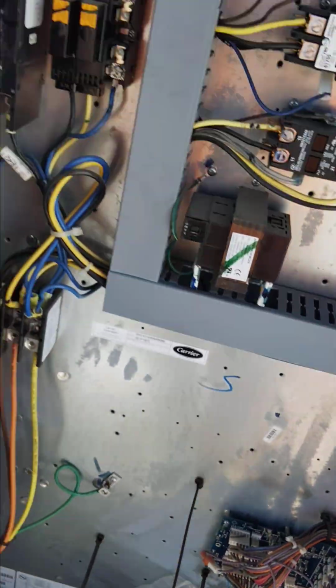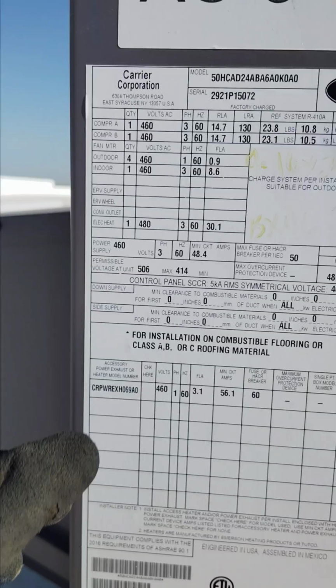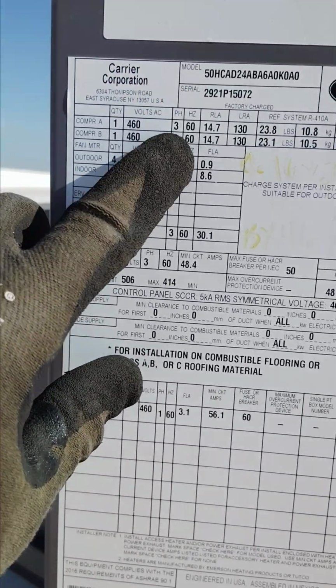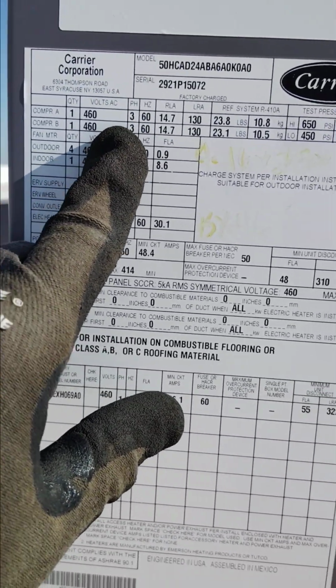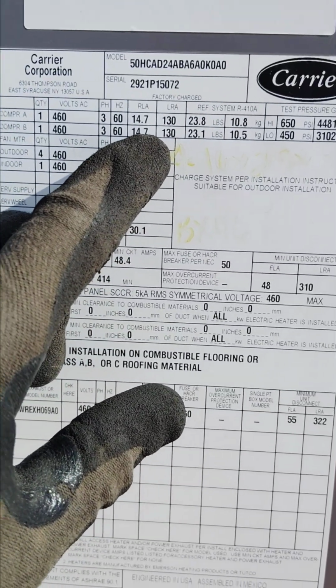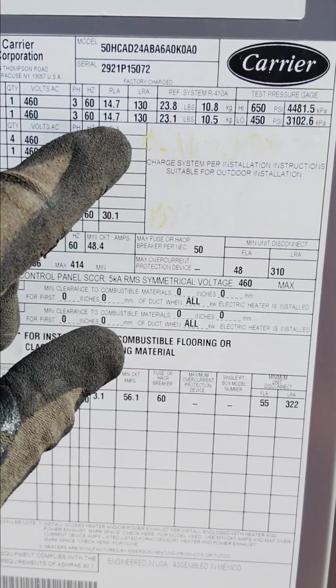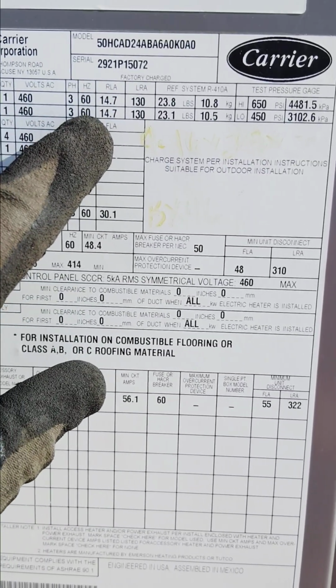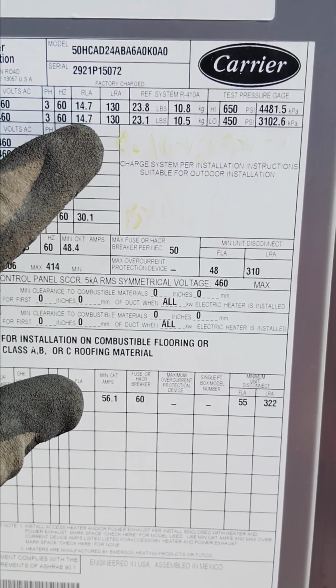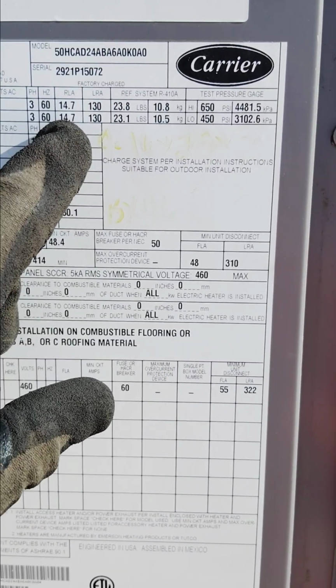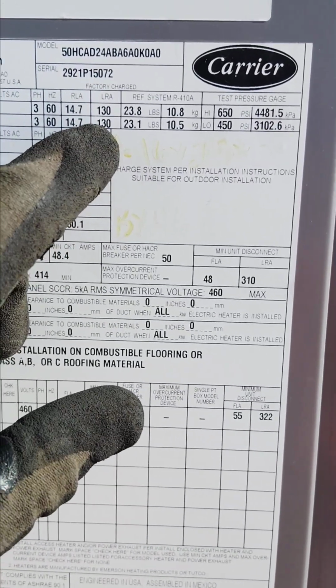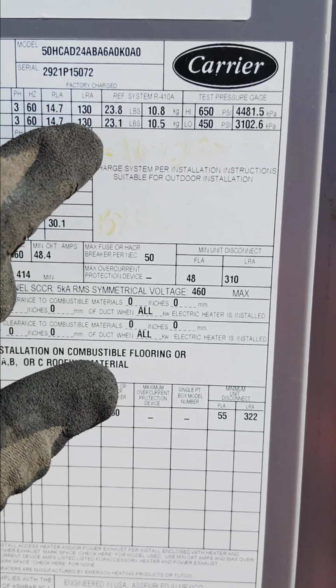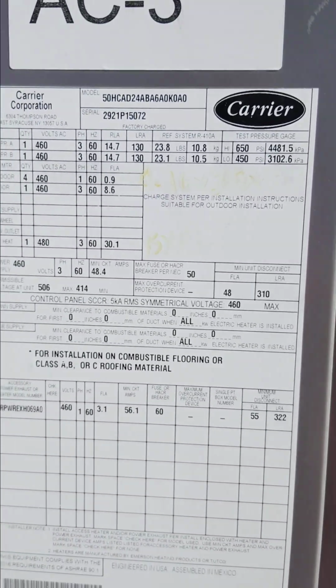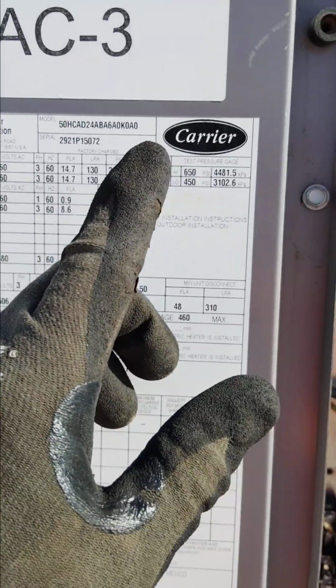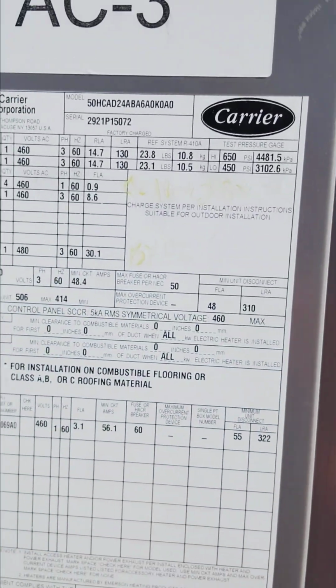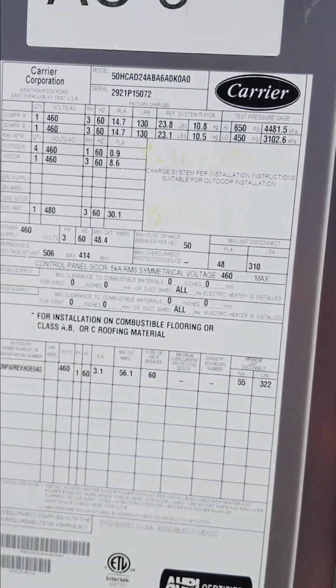As you can see here on the nameplate, these compressors are 3-phase, and it shows the running load amps and the locked rotor amps. So it's supposed to be operating within 14.7. That's for the running load, but normally it's gonna be below that. Once that compressor is locked up or something and it's pulling locked rotor, it's gonna maybe trip the whole unit, and maybe the compressor is gonna be bad at that point, because on these compressors you can't really put a hard start kit or anything on it.